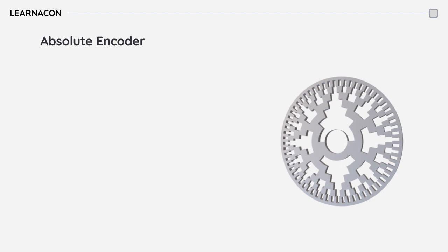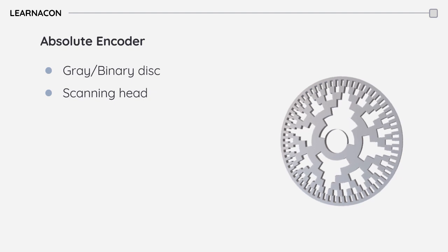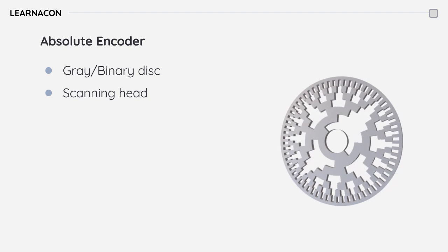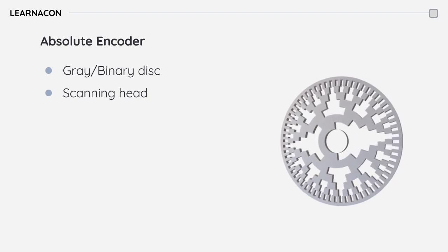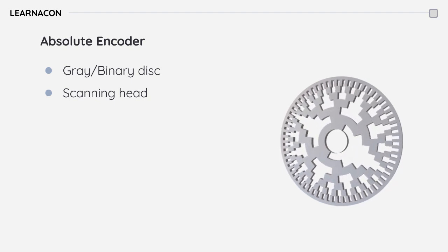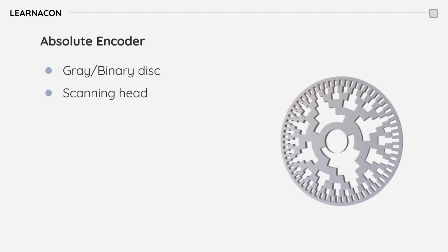A typical absolute encoder is made of a gray or binary coded disk and a scanning head. The code disk is mounted on the encoder shaft and rotates. The number of tracks on the disk depends on the encoder resolution. An encoder with a higher number of tracks offers a wider range of resolution.